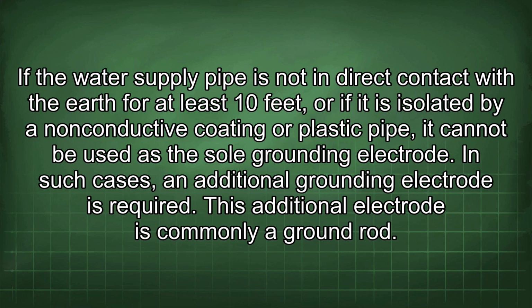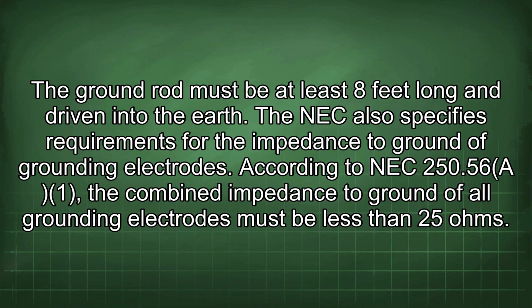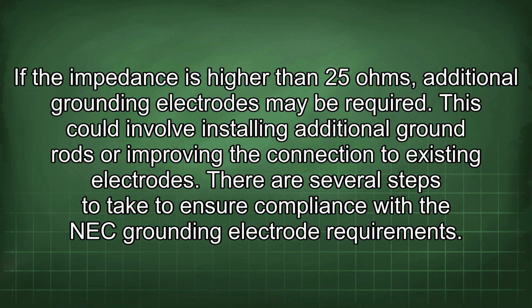This additional electrode is commonly a ground rod. The ground rod must be at least 8 feet long and driven into the earth. The NEC also specifies requirements for the impedance to ground of grounding electrodes. According to NEC 250.56, the combined impedance to ground of all grounding electrodes must be less than 25 ohms. If the impedance is higher than 25 ohms, additional grounding electrodes may be required. This could involve installing additional ground rods or improving the connection to existing electrodes.